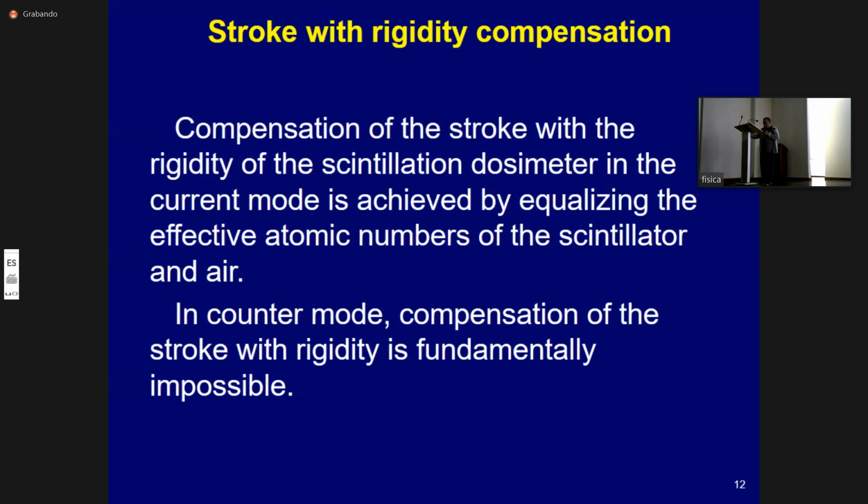and spectrometry. The dependence curve of the detector sensitivity on the energy of gamma radiation doesn't have a horizontal section. Therefore, the uncompensated energy dependence of the sensitivity limits the use of scintillation detectors in the counter mode for dosimetry. And it limits their use to measuring only radiation with a certain spectral composition.